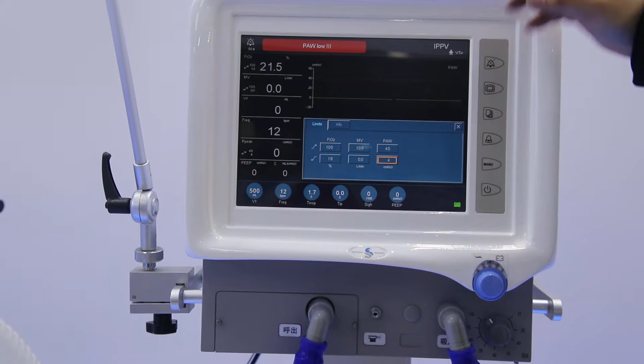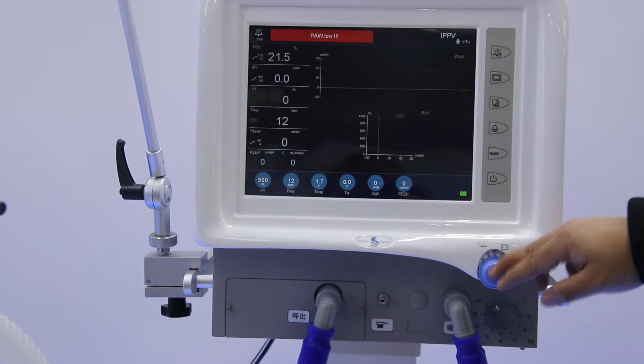The third button here is for changing the ventilation mode again, after a patient has used it or when changing to another patient. The fourth one here is the alarming area. It also shows the alarms here. It means the history alarm. After several months, if the engineer comes to do the maintenance, then they will know what problem was caused to the ventilator, and we will know how to fix it. And here is the limits. The upper limit and lower limit we can change for different alarming functions.